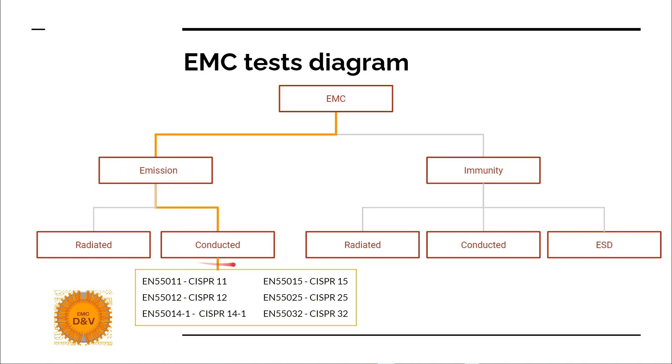Here we will be having several tests. One of these tests is voltage disturbances, and we have standards associated with these tests. EN 55011 is for medical equipment, laboratory equipment, and industrial equipment.